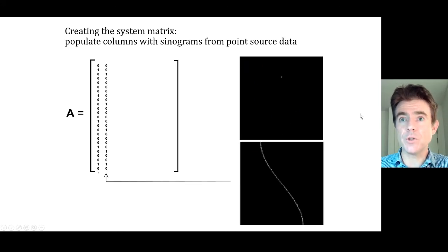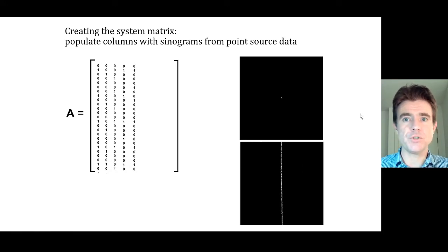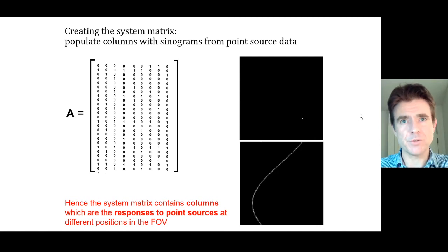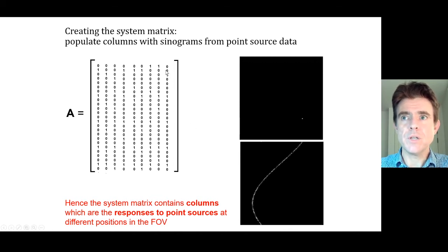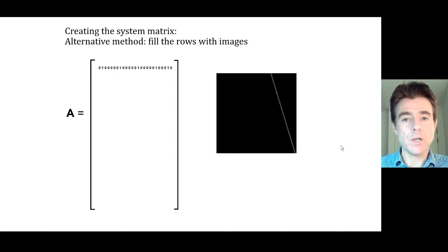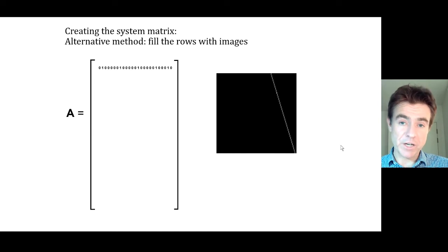We can do this for lots of different point sources at different positions inside the scanner field of view. We're just visiting different elements of the input parameter vector that represents the object — the reconstructed image, if you like — and for each one we need a column of the system matrix that models the mean response to a point source in that location. Hence the system matrix contains columns which are the responses to point sources at different positions in the scanner field of view.